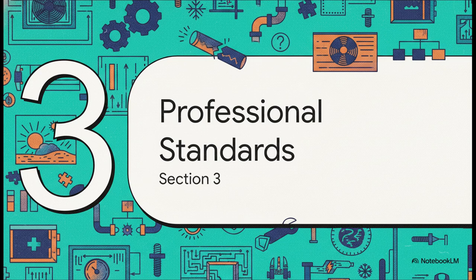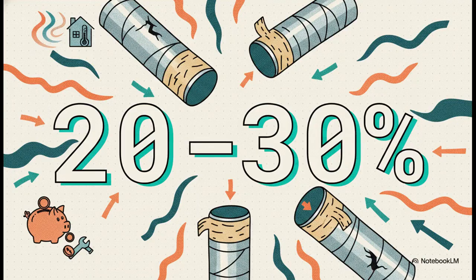When things break down this severely, guesswork just doesn't cut it. Section 3, professional standards and solutions. What is truly staggering here is a single number, 20 to 30%. That is the amount of heated or cooled air that is entirely wasted through leaky, improperly sealed ductwork in a typical home. Imagine that, paying for 100% of your energy bill but only actually feeling 70% of it? No way! This is exactly why professionals don't use standard duct tape, which ironically fails pretty quickly on actual ducts.